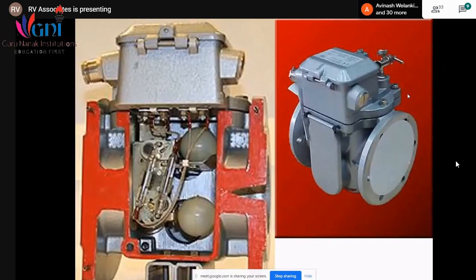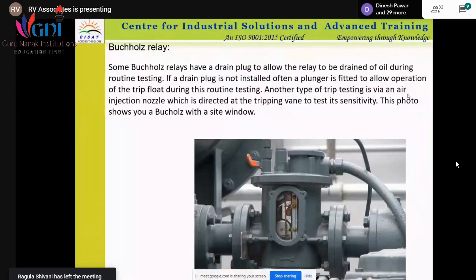We know where it is connected. We connect it between the main tank and the conservator. This is the Buchholz relay. It will give you an alarm, and it will trip if the fault is more serious. That means if there is a serious fault, the transformer has to be tripped, and the same function is done by the Buchholz relay.